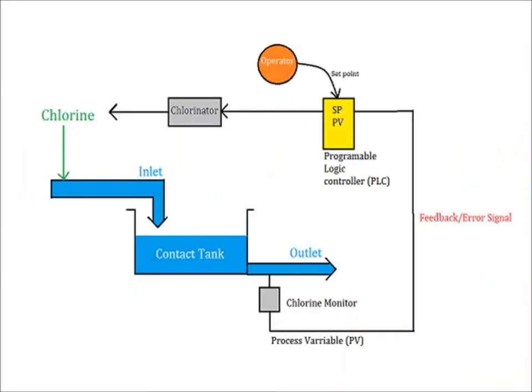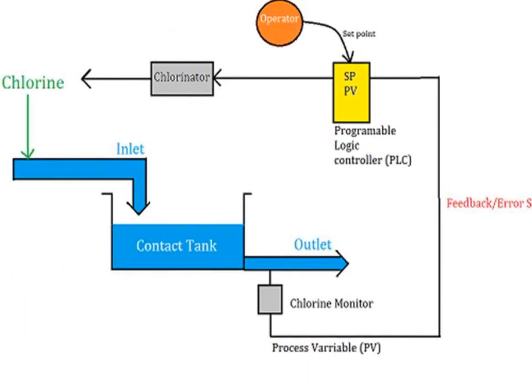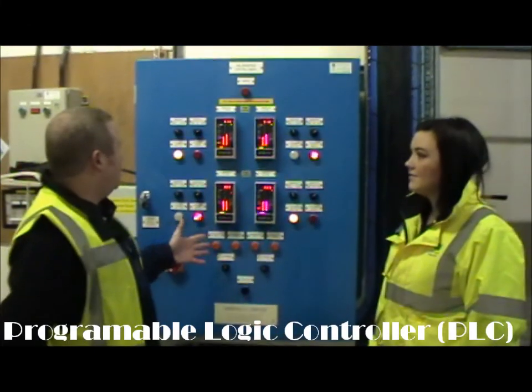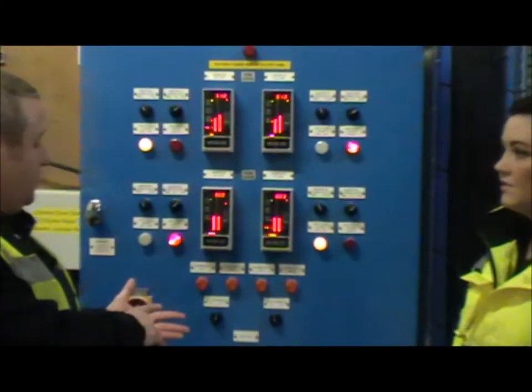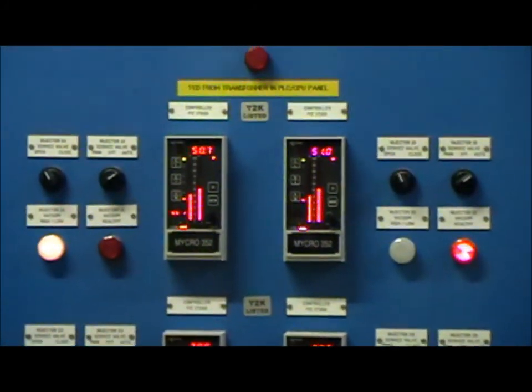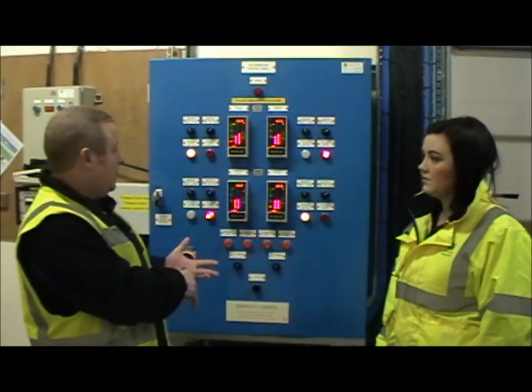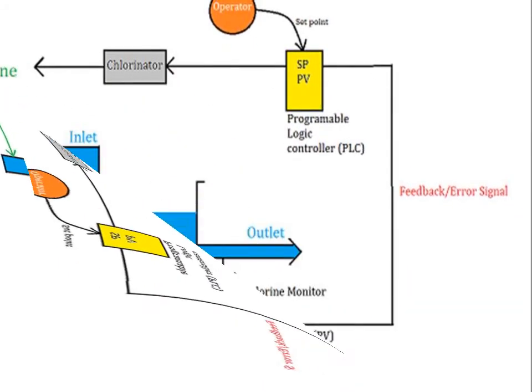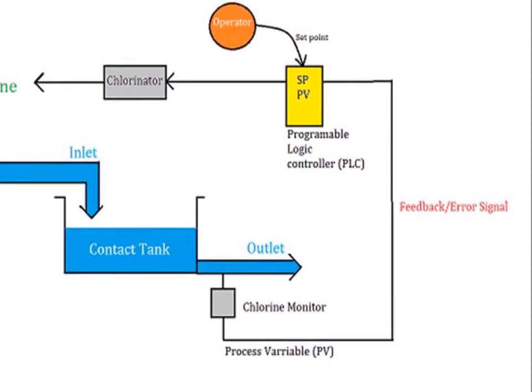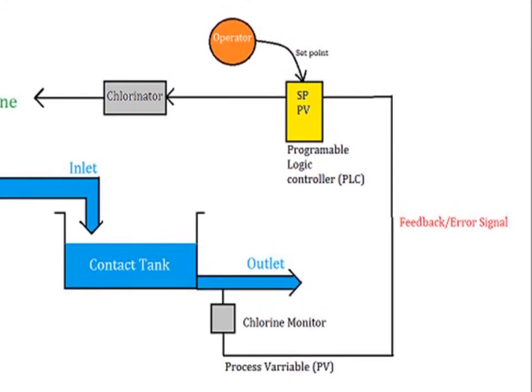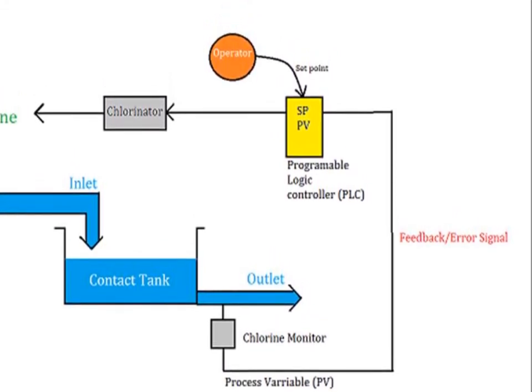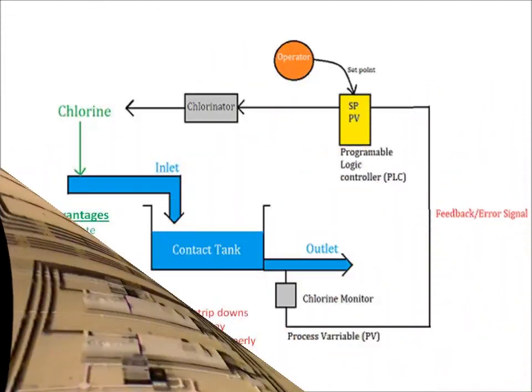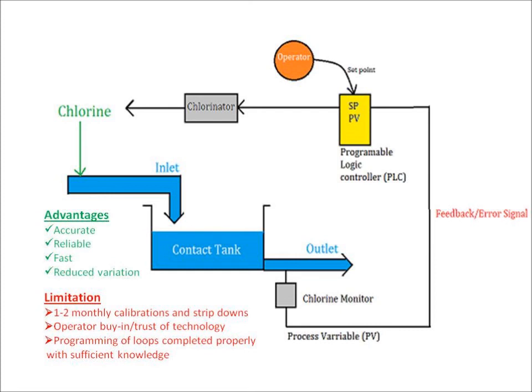Here we have a diagram of a closed loop chlorine control system for a water treatment works contact tank. The operator inputs a set point within the SCADA control system, which is sent to the Programmable Logic Controller — these are the actual controllers that control our plant. They take basic signals such as the flow through the plant and the chlorine signal measured at the tank outlet, and then they look at that information and write an output. Chlorine monitors collect a sample from the contact tank outlet and send a process variable to the logic controller.